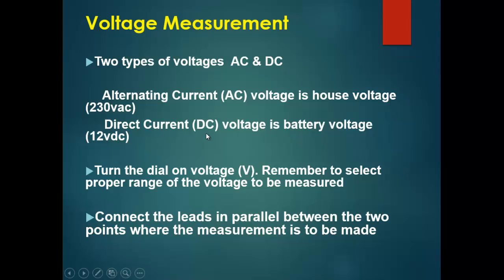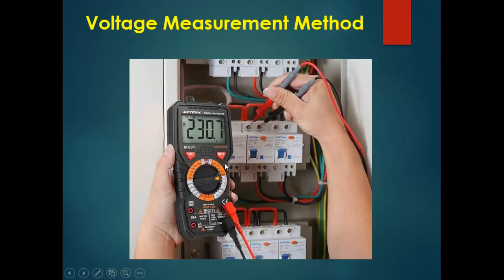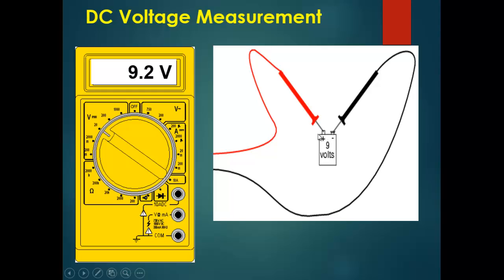First, properly select between the two voltages depending on which you want to measure, then turn the dial to voltage and select the proper range — remember to select the next higher value. Connect the black and red leads in parallel between the two points where measurement is required. As you can see here, the person is measuring the voltage between two terminals and the meter is showing 230 volt AC.